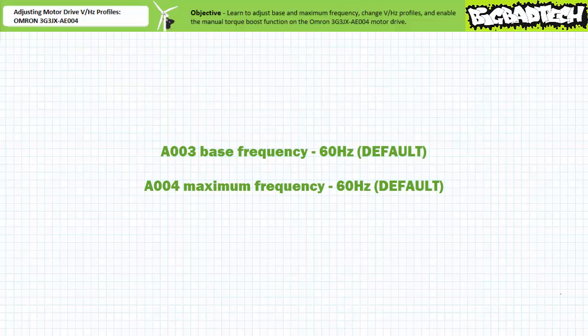Let's now learn to display the current entry and change the base and maximum frequency. Extended function parameter A003, base frequency, is user adjustable from 30 hertz to the current maximum frequency entry A004, currently set at the default 60 hertz.